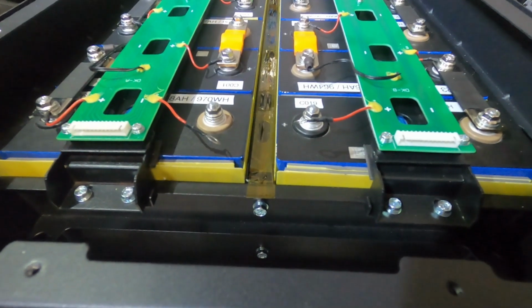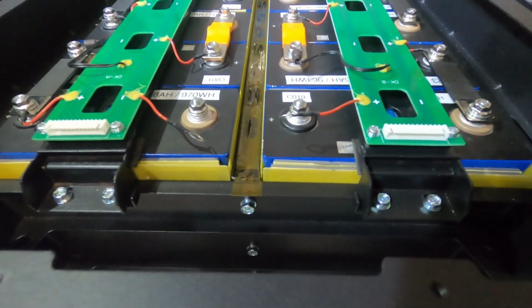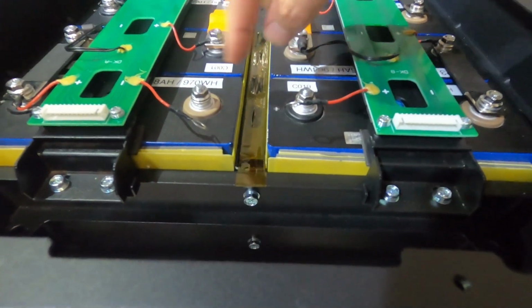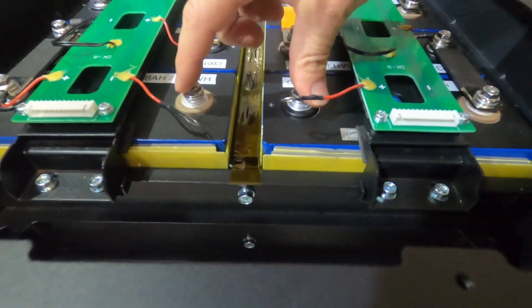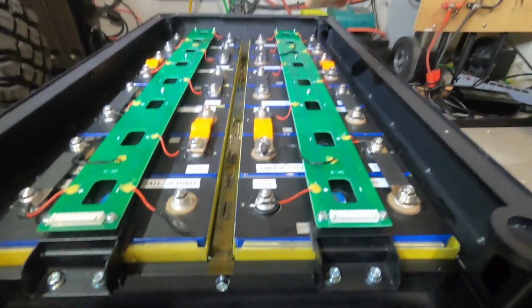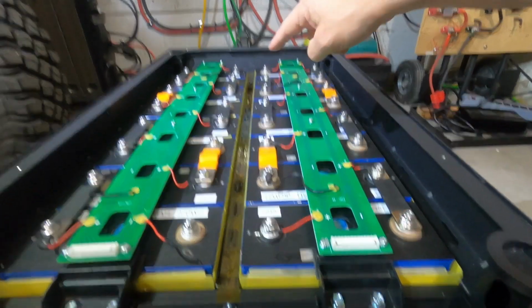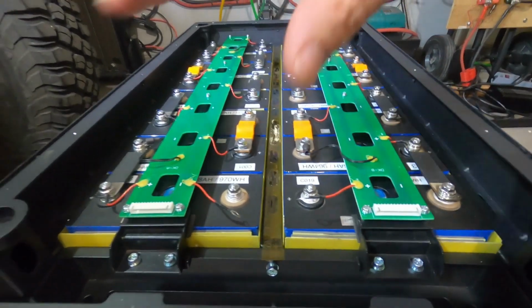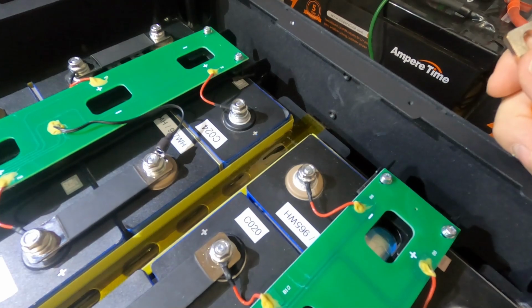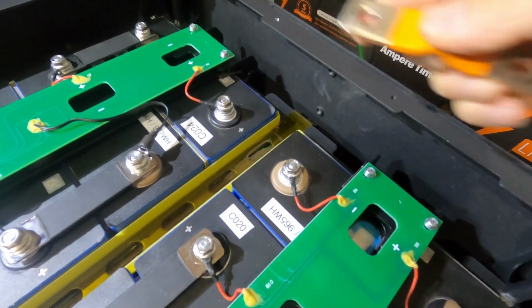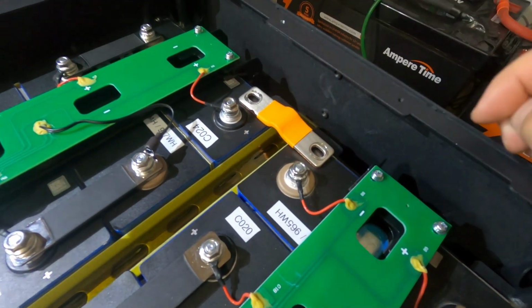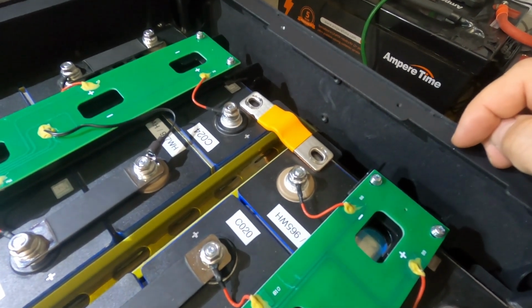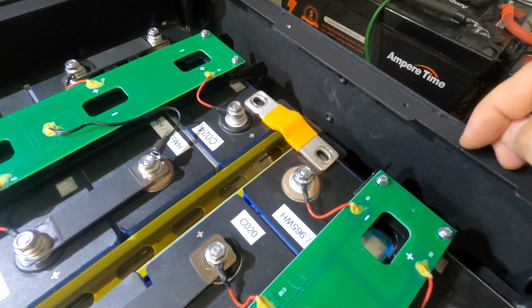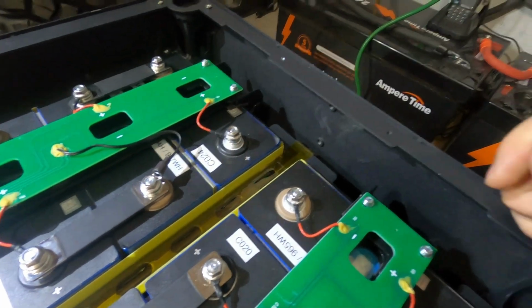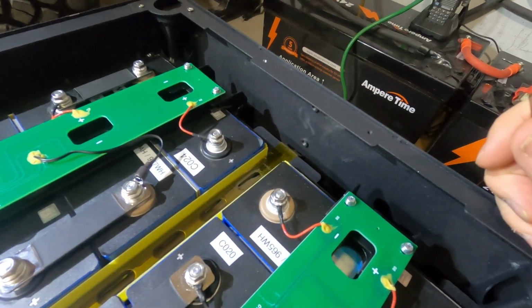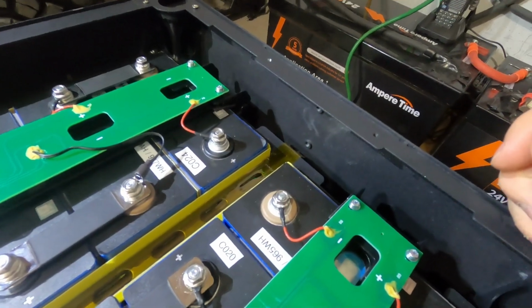The first step is to connect the BMS mains to the main positive and main negative. Currently there is no voltage on our positive and negative because I have the bridge connector on the back disconnected, so right now we have two separate 24 volt packs. The second step is we'll come to the back of the battery and connect up our main bridge bus bar, connecting the two 24 volt packs into a single 48 volt pack. At that point, the mains at the front of the battery, the main positive and main negative, will be energized.